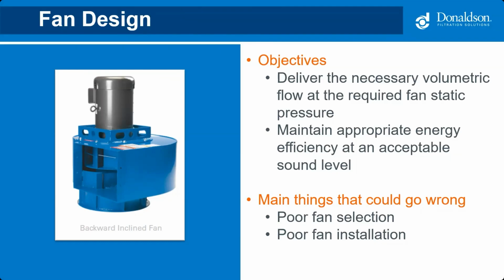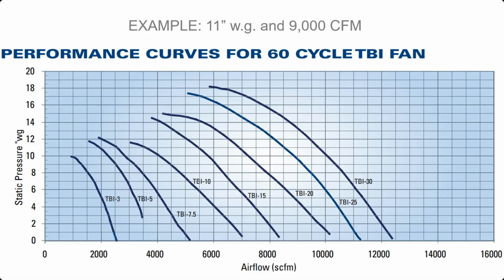Fan challenges generally fall into 2 categories: poor fan selection and poor fan installation. The fans are sized based on the system's total static pressure and the required airflow. For example, let's say I need to size a fan for the example I gave you earlier, 11 inches of water at an airflow of about 9,000 CFM. We use the static system pressure of 11 inches with an airflow of 9,000 CFM.